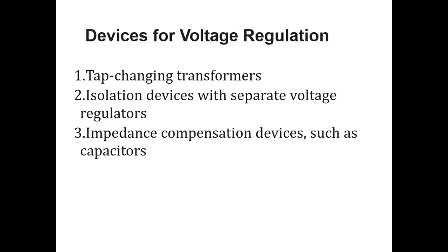Now the next thing that we are going to discuss is isolation devices which separate the voltage regulators. Such devices are incorporated in the power system so that we separate the voltage regulators. This is also another device that we can use for the improvement of voltage regulation. Next, impedance compensation devices such as capacitors. Most types of load are inductive in nature, so to improve the voltage regulation of the power system, you need to add capacitors in parallel with that, so that you will get improvement in the voltage regulation.